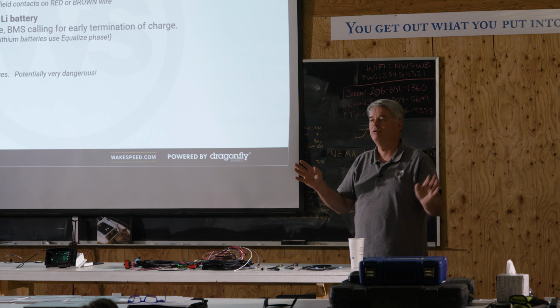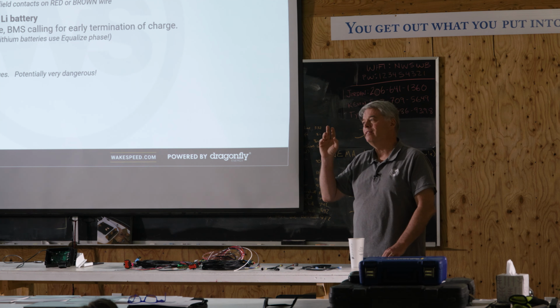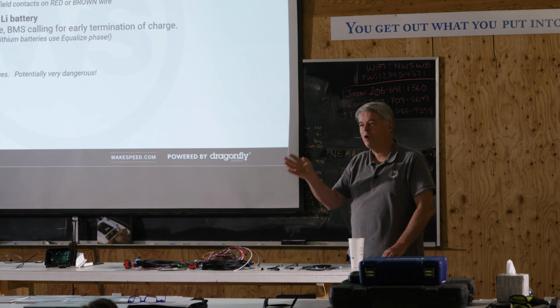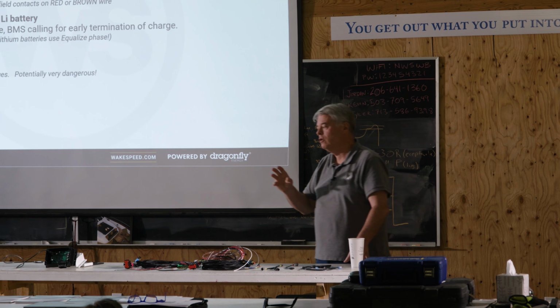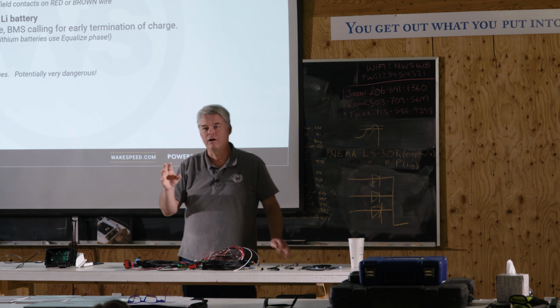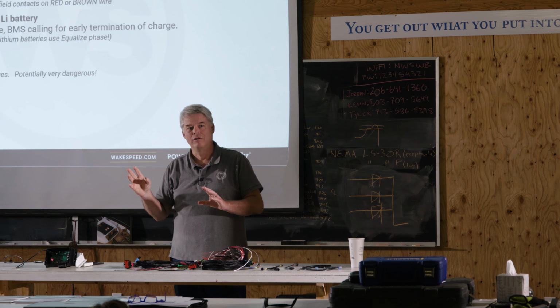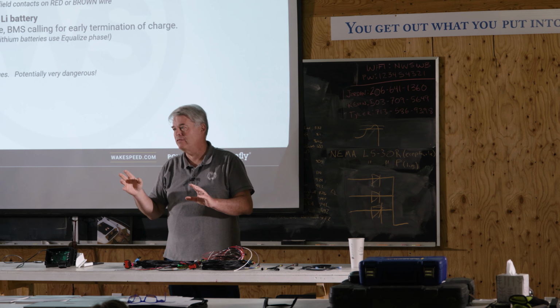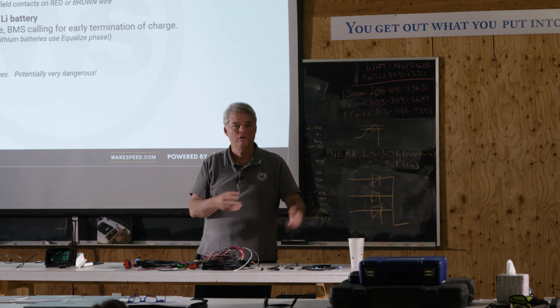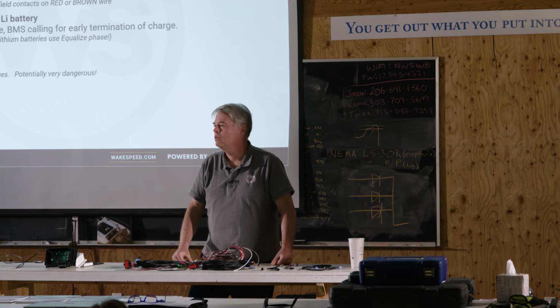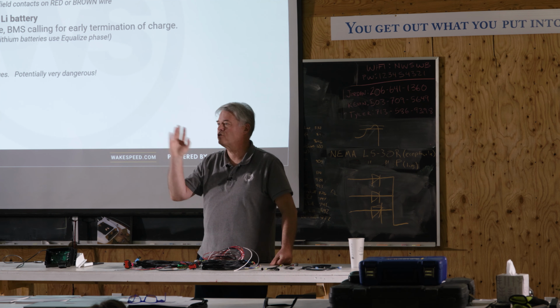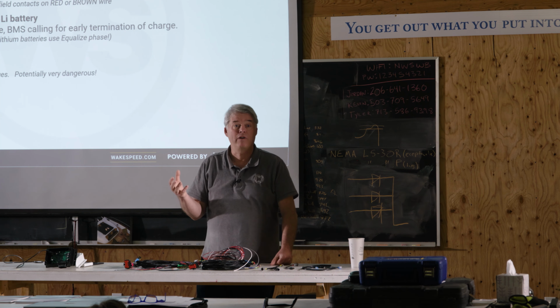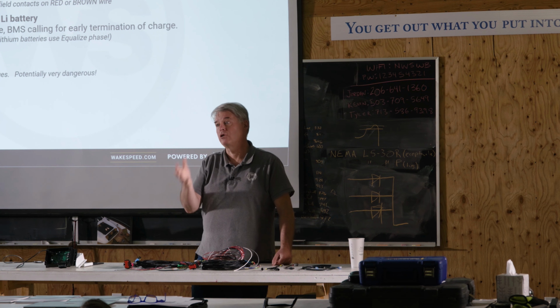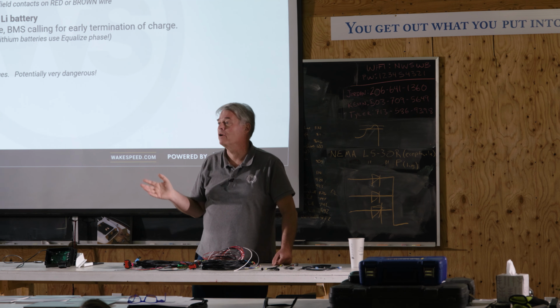Here's what had been done. They had installed the system correctly. We recognized what had happened is the operator had read on a forum somewhere that if you're using your van to drive and get groceries and Slurpees, turn your battery off. Disconnect your lithium battery, don't stress it. You know, it's not bad advice. Maybe that's not a bad idea. There's no reason to charge and discharge when you're just getting the Slurpee, right?